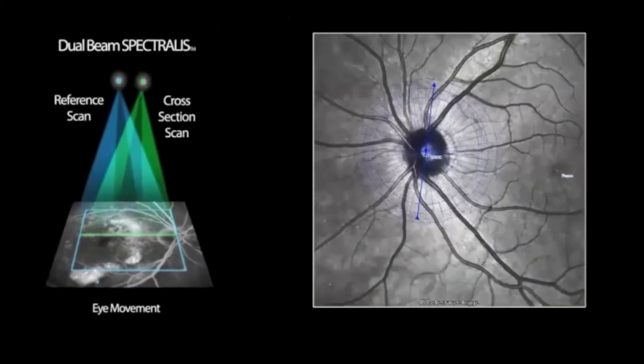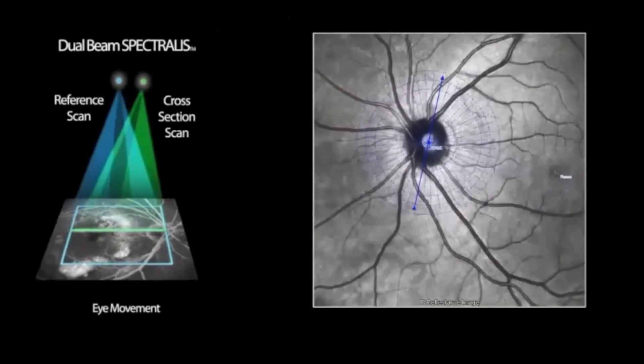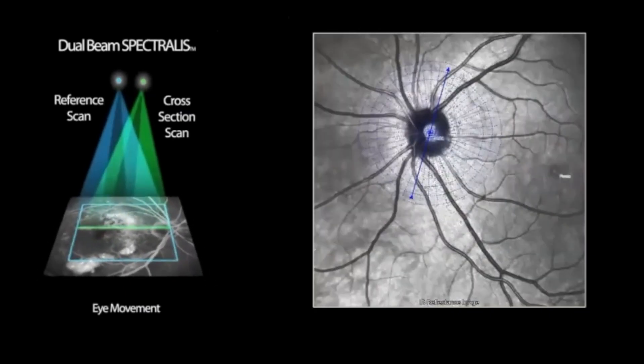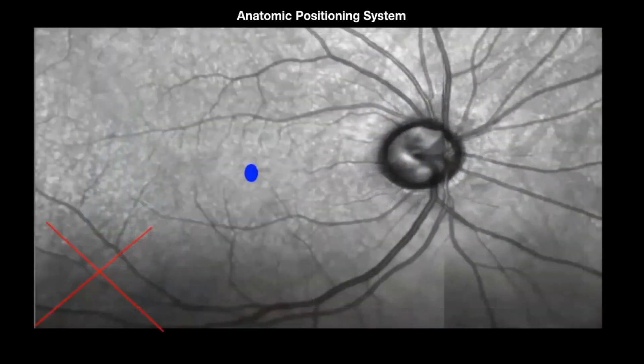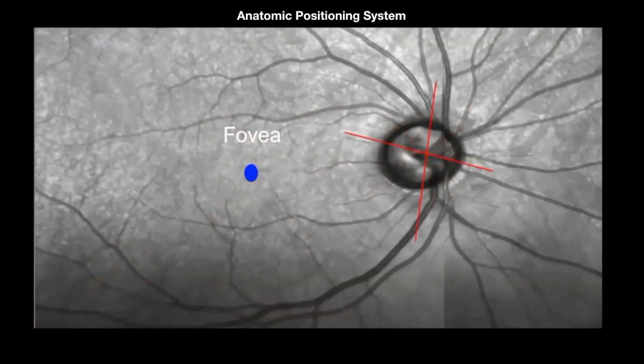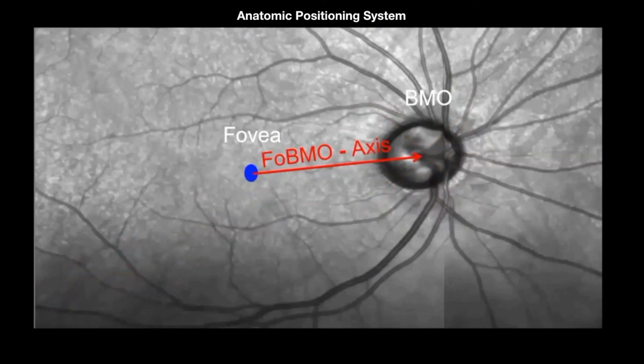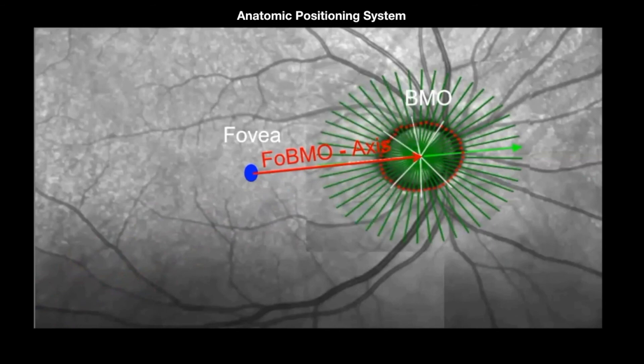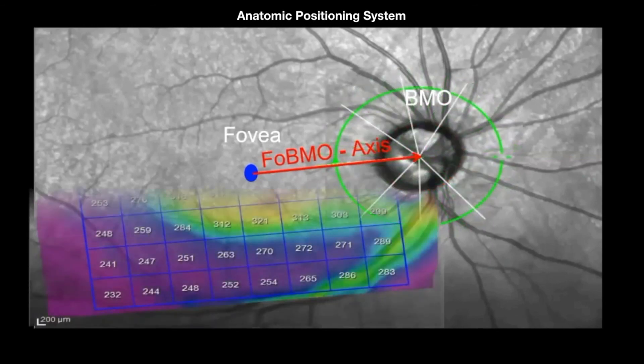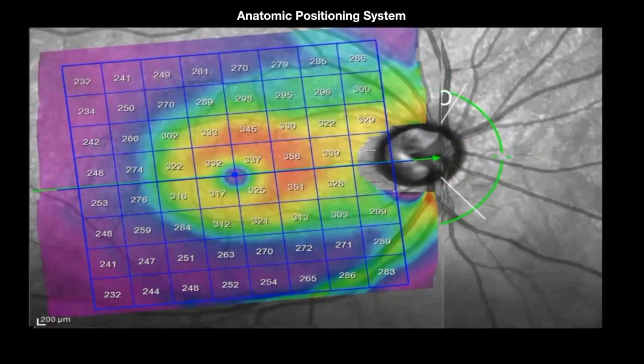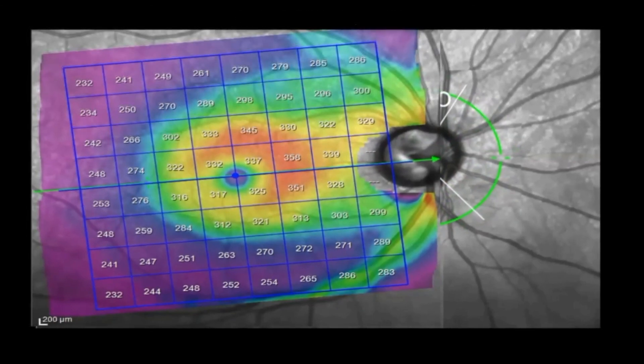With Spectralis, there is a dual beam scanner to detect minute eye movements during the examination. With the Glaucoma Module Premium Edition, the same piece of tissue is examined during follow-up, which is very important for detecting glaucomatous progression. With the Anatomic Positioning System, first the foveal centration is marked, then the BMO centration, then the fovea-BMO axis is plotted, followed by the 24-line scan examining 48 BMO positions, followed by the circular scan examining RNFL thickness, and finally the examination of the ganglion cell layer.